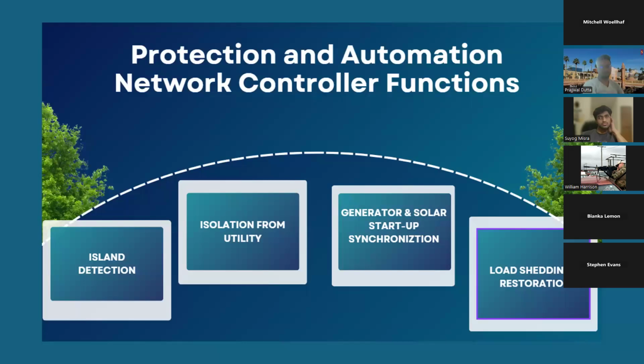In this microgrid, the controller is programmed to manage key protections and automation tasks. For instance, island detection. That is when the utility grid fails or goes out of tolerance. The controller detects this through frequency and voltage sensing relays, signaling the microgrid to enter island mode. Secondly, isolation from utility. Using automated breakers and control logic, the microgrid electrically separates itself from the main utility grid to avoid backfeeding and ensure personnel safety.